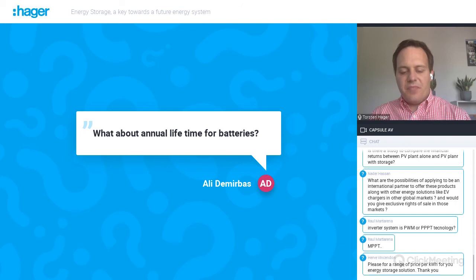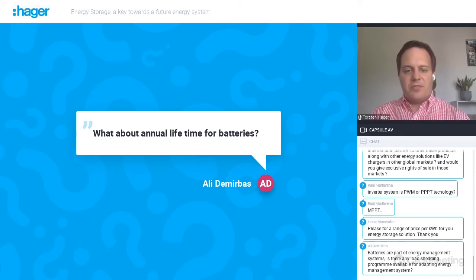On the other hand, we take care with different measures to limit the load on the battery and not affect its lifetime—by reducing currents as much as possible, taking care about temperatures, and keeping them at a good state of charge. For example, if there are periods in the year when you don't need the full capacity of the battery, you might not charge it completely full, but keep it at a good level to increase calendric lifetime. All these measures are taken into account to increase battery lifetime.